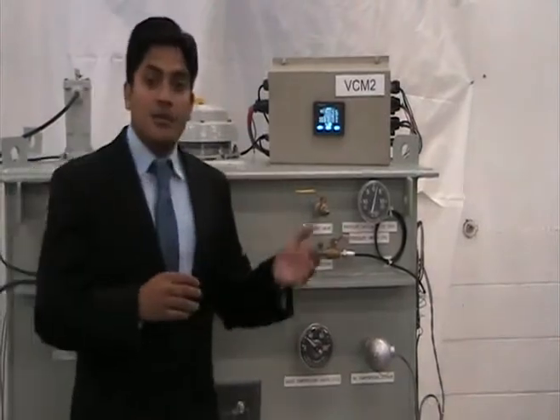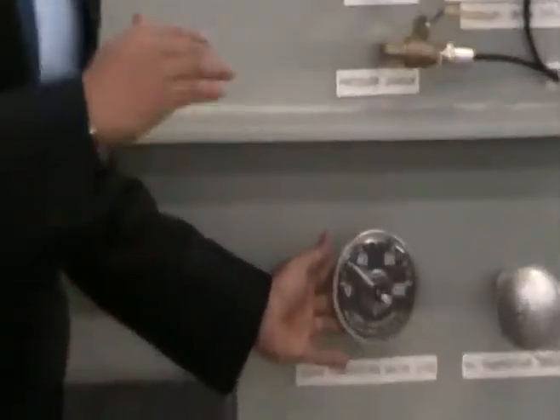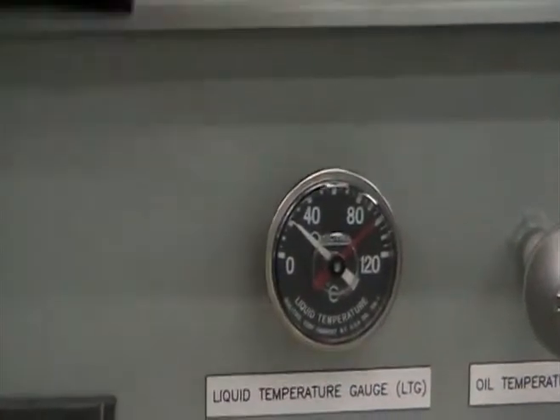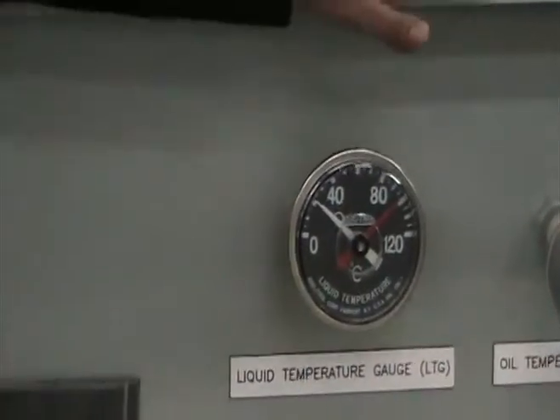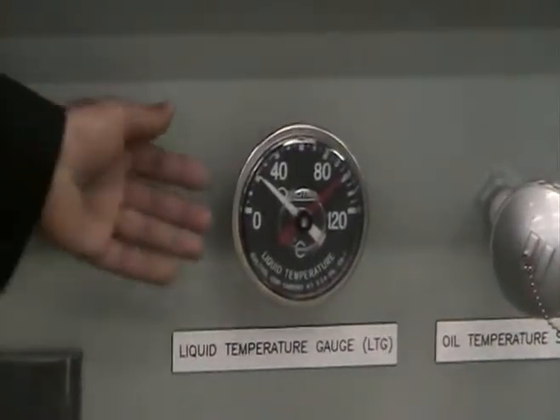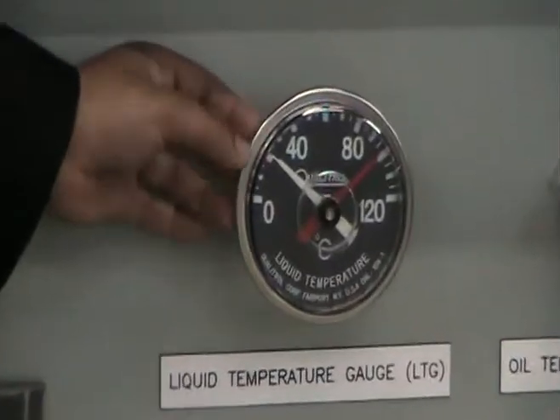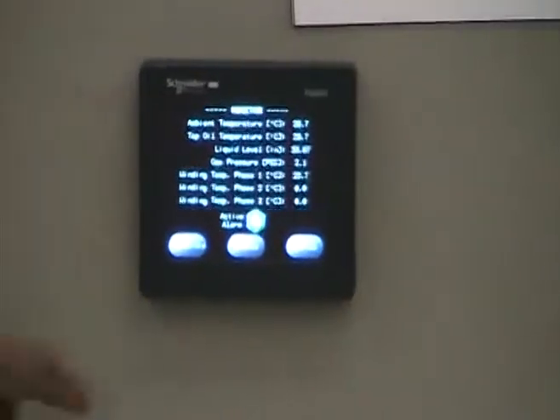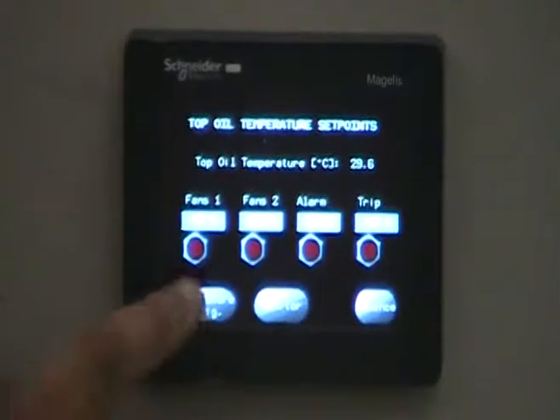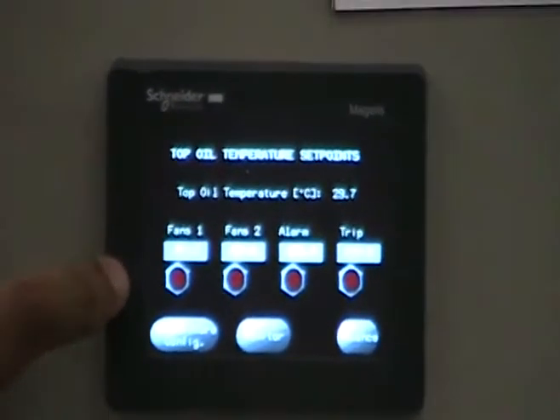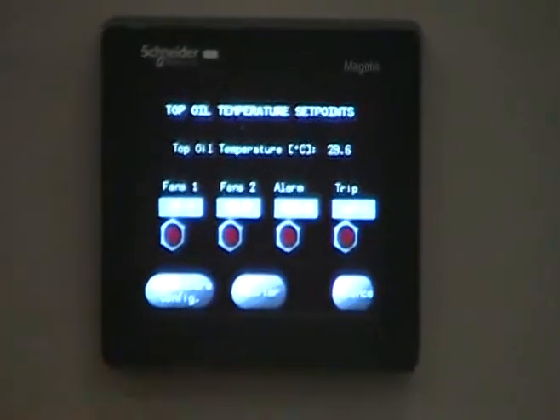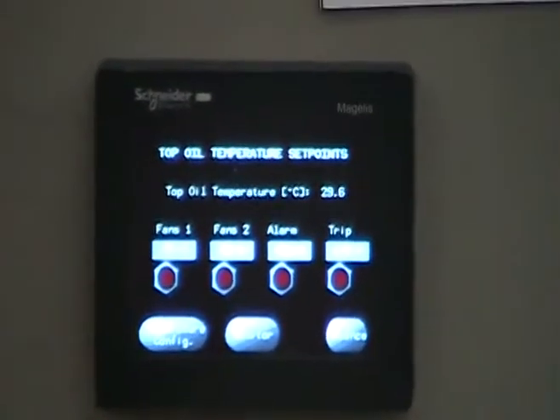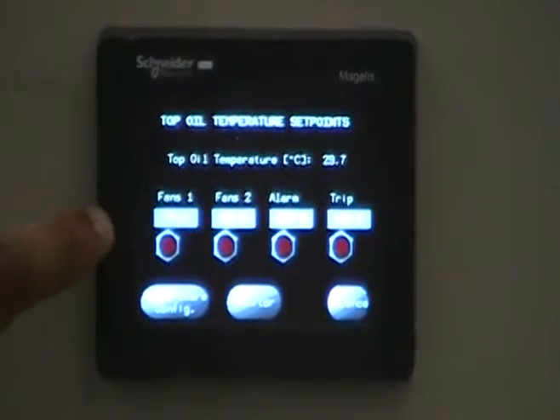Now I will demonstrate how VCM2 can measure and monitor the transformer's liquid temperature. We have used a Qualitrol liquid temperature gauge to compare the VCM2 results. Our model is at ambient temperature, so the oil is also at ambient temperature. You can see the gauge shows the oil temperature as 29 and the VCM2 shows the reading as 29.7. Also you can see here we have various set points for fan stage 1, fan stage 2, alarm and trip. The alarm is deactivated because the measured value is less than the set value.